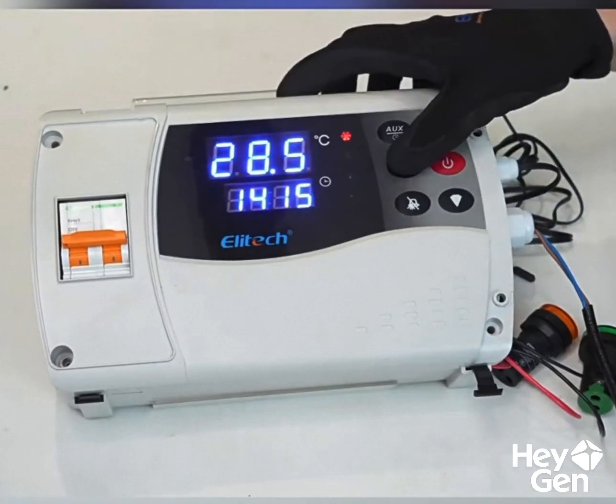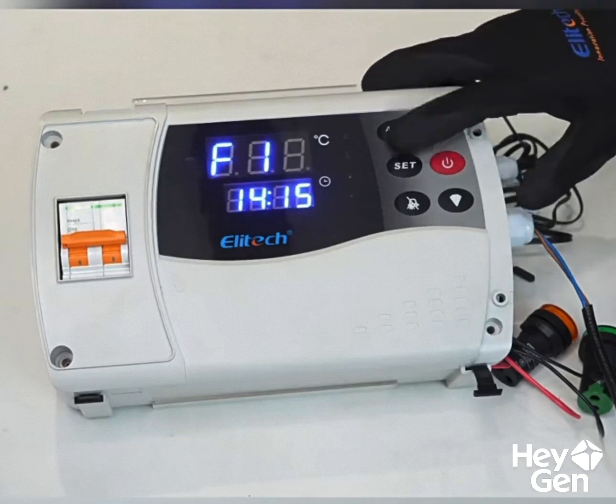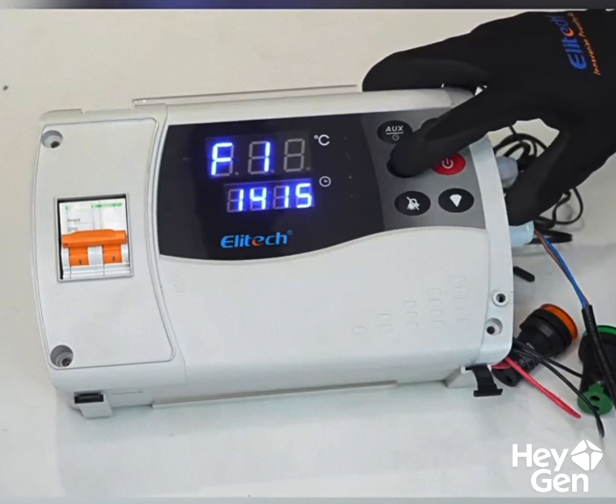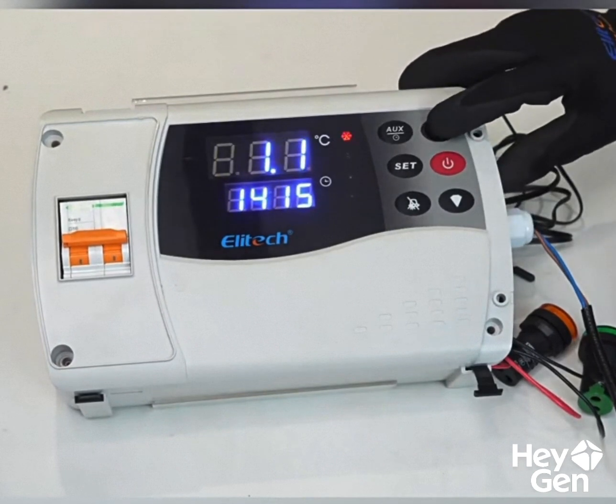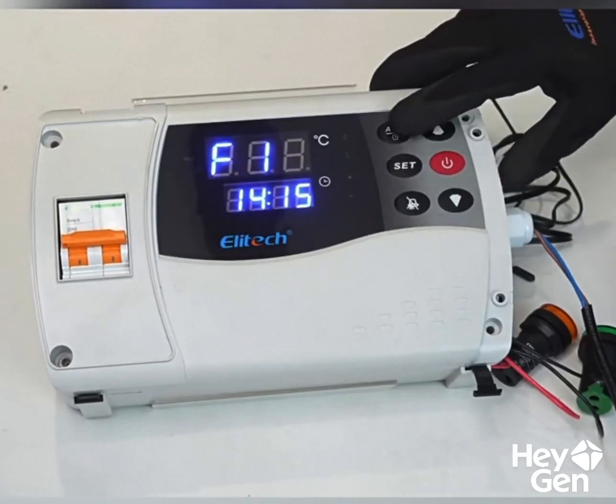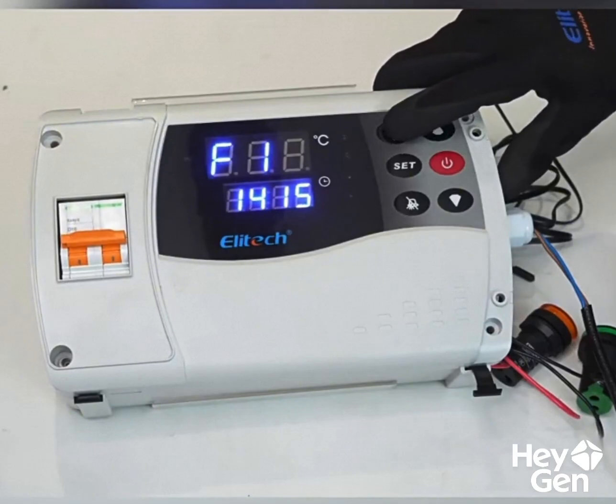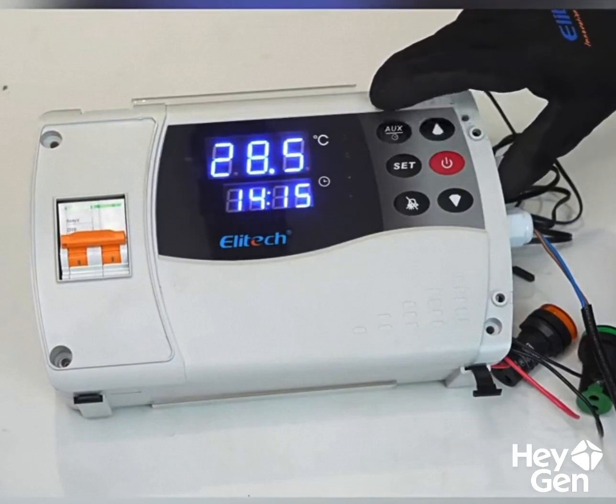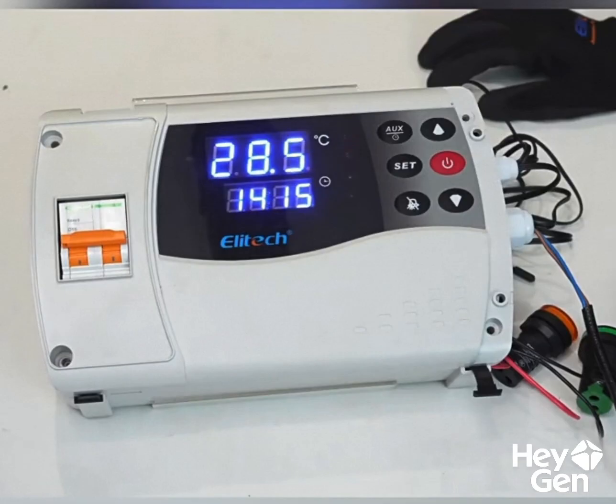Press and hold the set button for 5 seconds until F1 appears. Then press set to enter the F1 parameter interface. Use the up and down buttons to set it to 3 degrees. Press set again and you can press the aux button to exit editing and save the previously set parameters. In this way, you can achieve cooling and heating switching between 7 degrees and 13 degrees above zero.